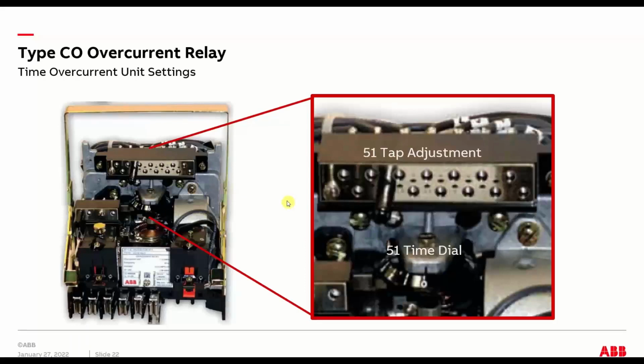So, as a quick tutorial on how to read these things: they look complicated, and if you walk up to one, it's very unclear what they're set to and what they do. So I want to do a really quick walkthrough on how to look at an old electromechanical relay and see what the settings are. For the time overcurrent, there's a tap and a time dial. The tap is literally a tap. It's little holes with a screw element that you can move between all these predetermined tap values, and that sets the pickup of the relay. And the time dial is literally just a little dial, with no notches, no detents. It's a continuous dial that goes from, say, 0.5 to 11.